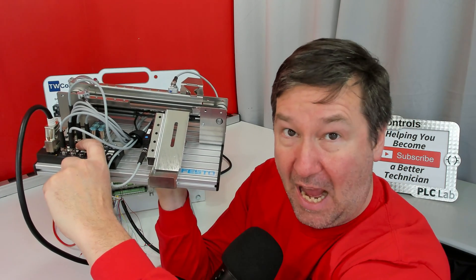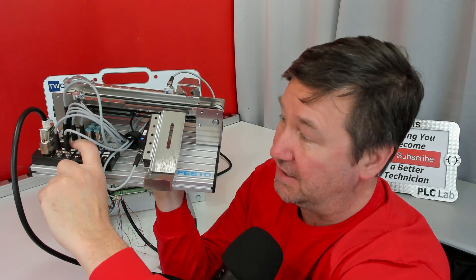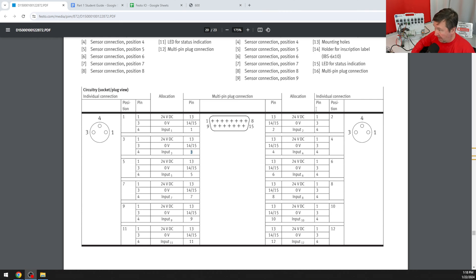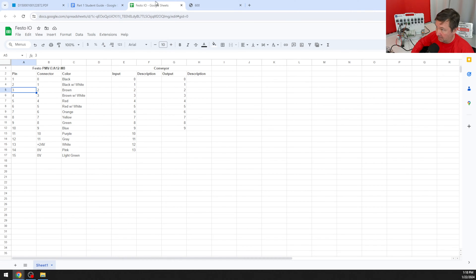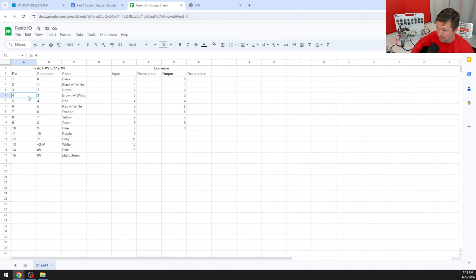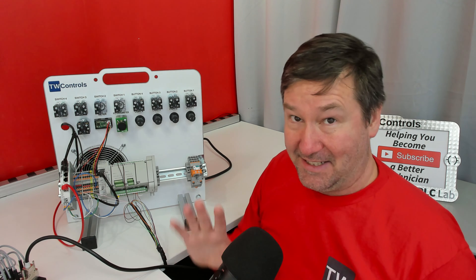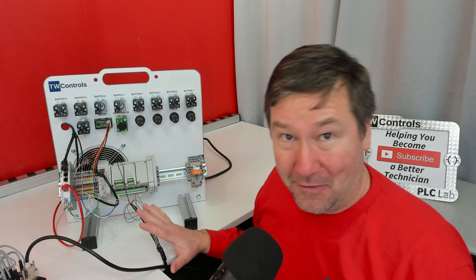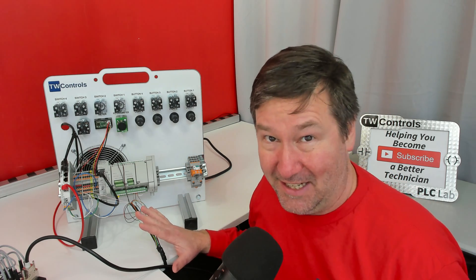Now we have three outputs on this one and those are going to be pins 2, 4, and 6. If we look over here pin 2 is black with white, pin 4 is brown with white, and pin 6 is red with white. And we're going to connect those to outputs 4, 5, and 6. Now that takes care of the wiring of our 15 pin connector.